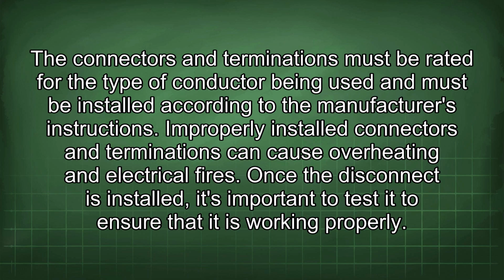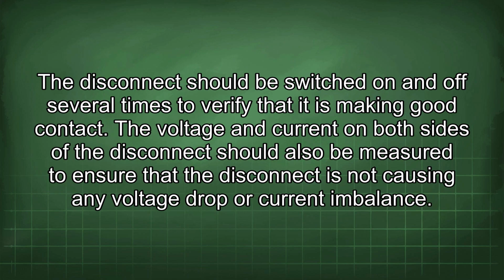Once the disconnect is installed, it's important to test it to ensure that it is working properly. The disconnect should be switched on and off several times to verify that it is making good contact. The voltage and current on both sides of the disconnect should also be measured to ensure that the disconnect is not causing any voltage drop or current imbalance.